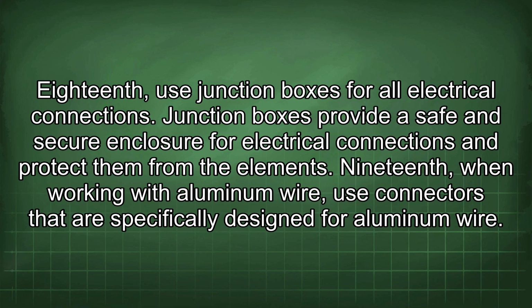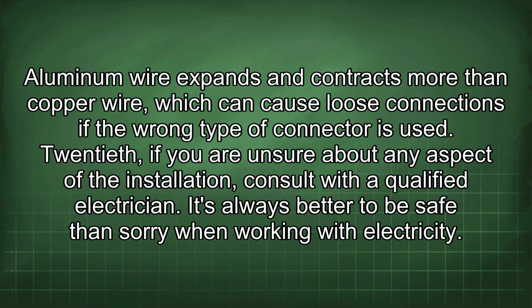18th, use junction boxes for all electrical connections. Junction boxes provide a safe and secure enclosure for electrical connections and protect them from the elements. 19th, when working with aluminum wire, use connectors that are specifically designed for aluminum wire. Aluminum wire expands and contracts more than copper wire, which can cause loose connections if the wrong type of connector is used. 20th, if you are unsure about any aspect of the installation, consult with a qualified electrician. It's always better to be safe than sorry when working with electricity.